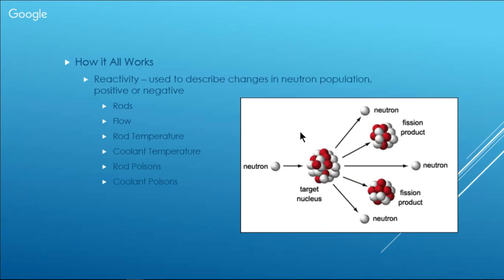It's one of the things that I've seen in numbers around 5 times 10 to the 10th, 4 times 10 to the 10th, neutrons per square centimeter per second. Right. And it also depends on what you have in the reactor. If you have xenon in there, that's going to change your flux density as well. Because, for example, after a shutdown or a scram, you actually have this big spike of xenon gas. And xenon is actually a neutron absorber as well. So that's going to affect your neutron density. You actually have to wait for that decay to go away before you start up again in many cases.